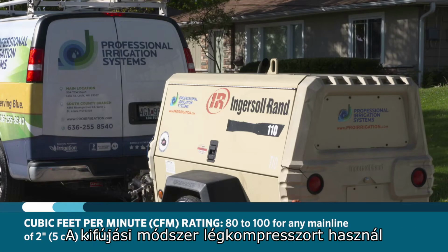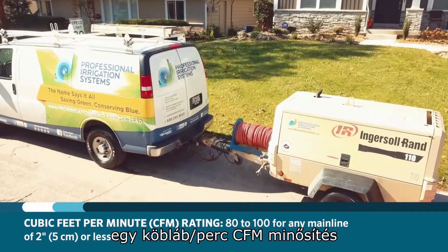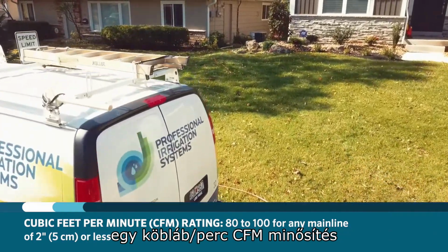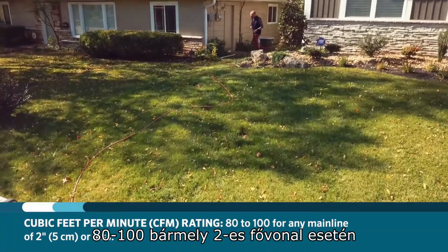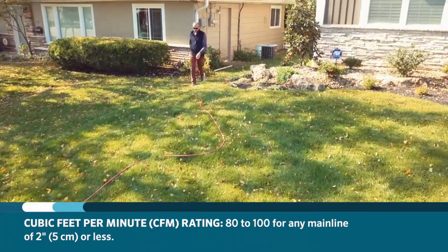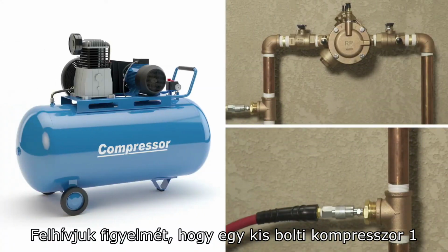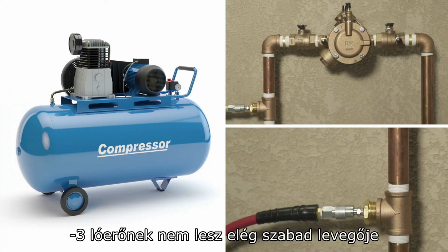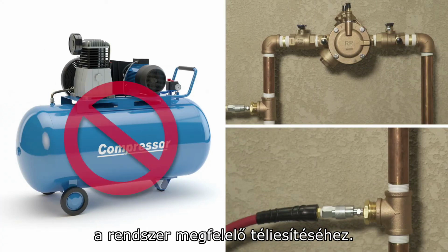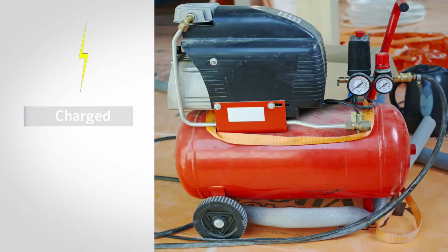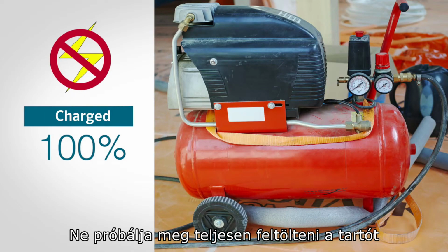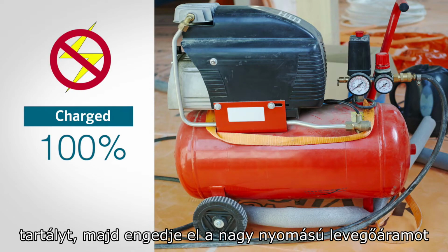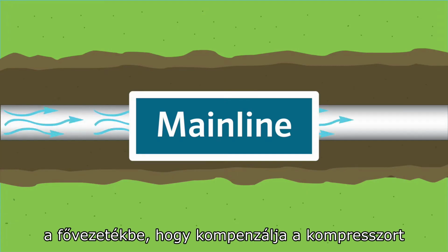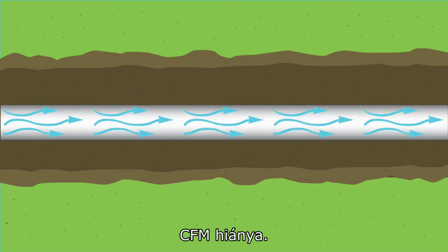The blowout method utilizes an air compressor with a cubic feet per minute (CFM) rating of 80 to 100 for any mainline of 2 inches or less. Please note that a small shop compressor, 1 to 3 horsepower, will not have enough free air to properly winterize the system. Do not attempt to fully charge the holding tank, then release the highly pressurized airflow into the mainline to compensate for the compressor's lack of CFM.